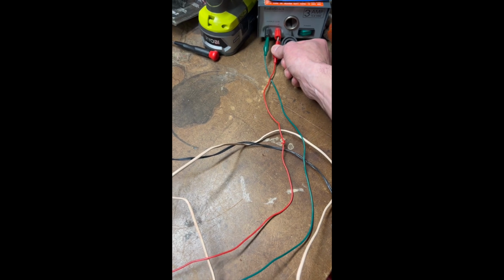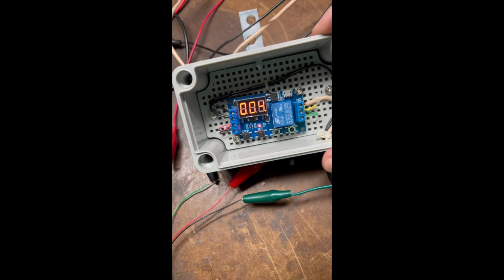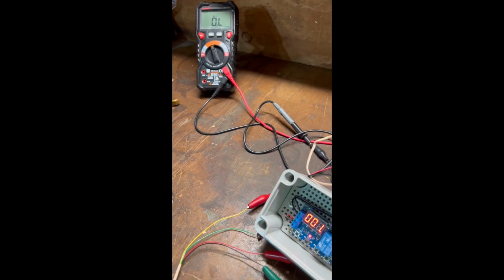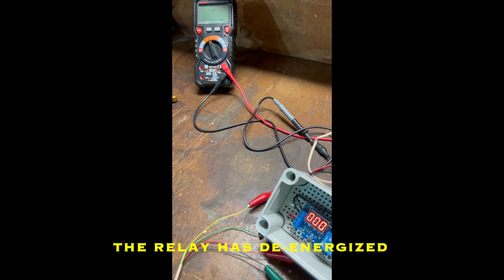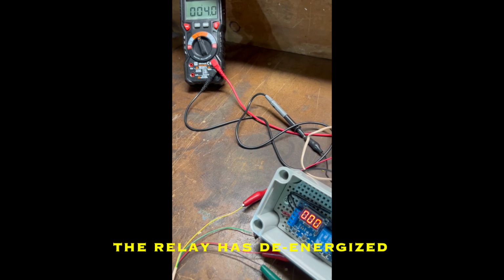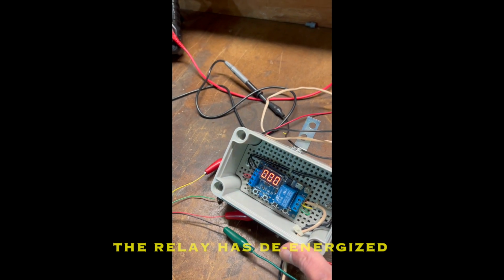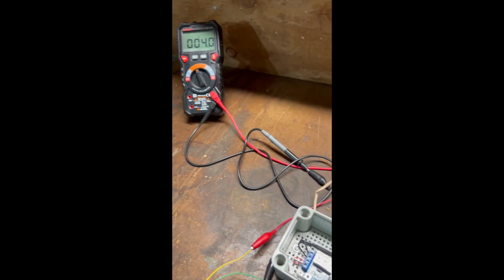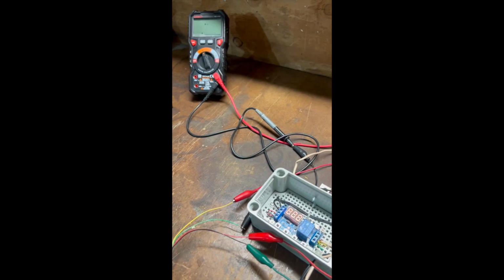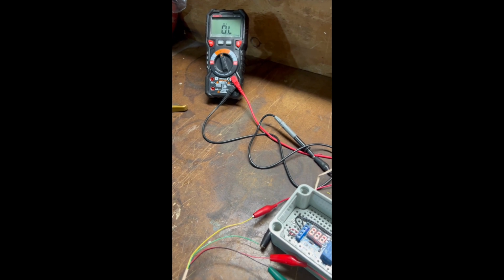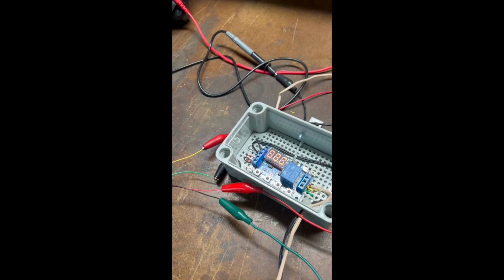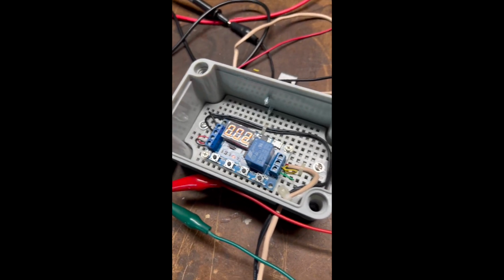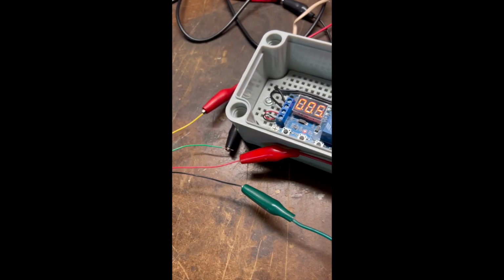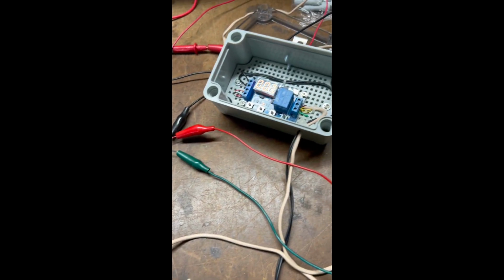But for now, we'll remove our trigger voltage by disconnecting this lead, and you'll see the display counts down 3, 2, 1, relay clicks. We are now in a closed position or an alarm position from my standpoint. Let's reapply the trigger voltage by connecting the power, the trigger voltage, and I can unhook that many times. I know it's hard to see on this display. Let me angle it a bit.